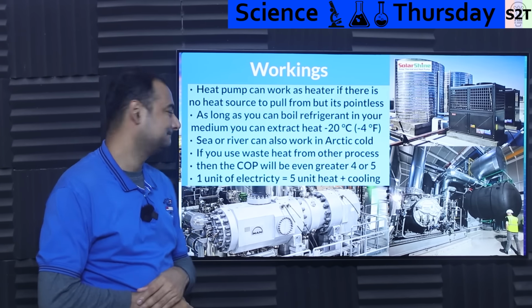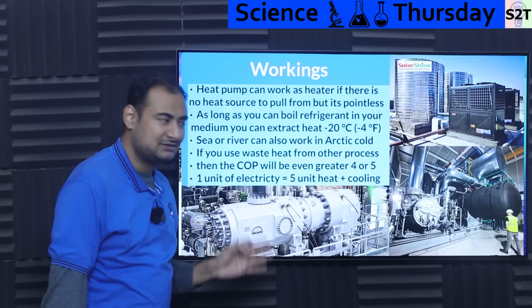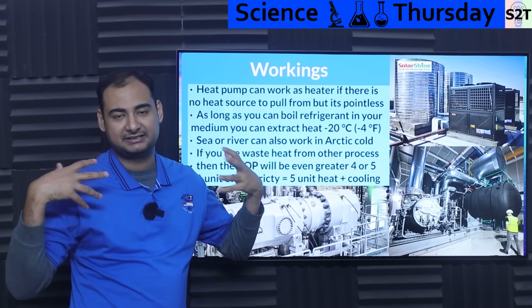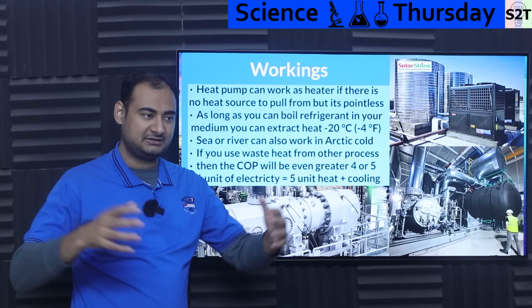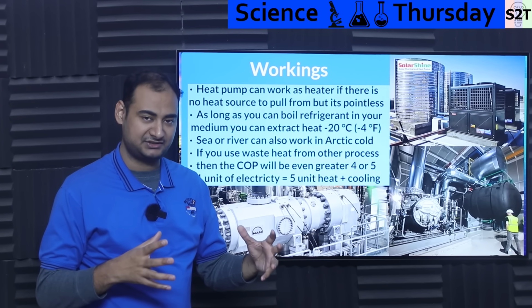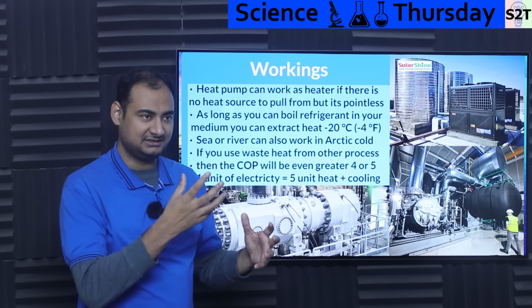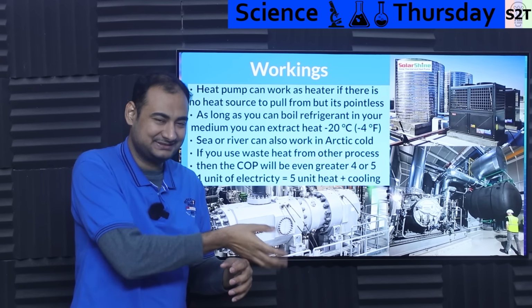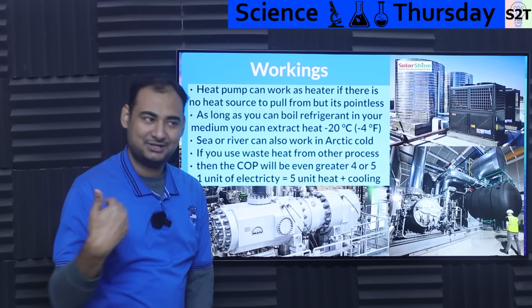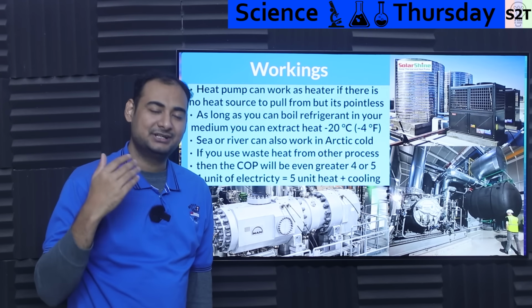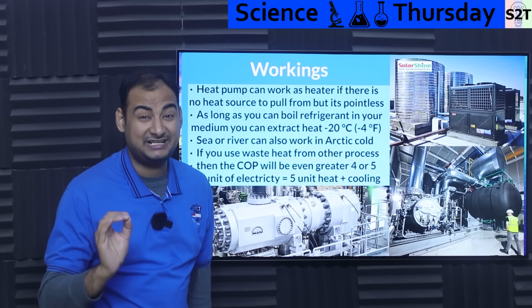And the best scenario is basically using waste heat. That's the sweet spot. You're not supposed to take heat out of places where it's not designed for. Let's imagine it this way: say you're pasteurizing milk. You heat it up, but then you also have to cool it down. At that point in time, that makes a complete loop, meaning you're heating and cooling at the same time. A heat pump in this scenario is perfect, it's optimum. Of course you can't reach 100% free energy, perfectly heating and perfectly cooling, but you can reduce power consumption by 20%.